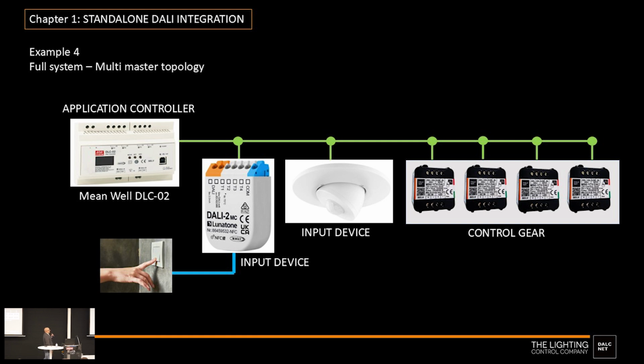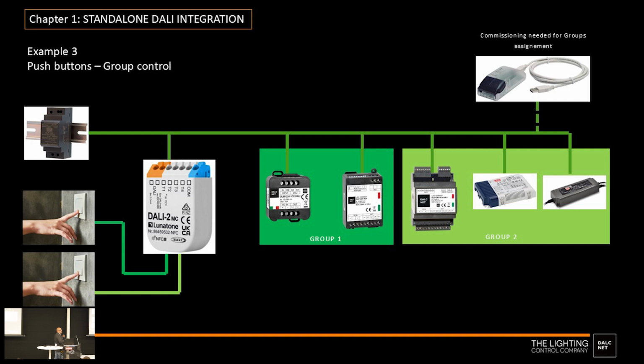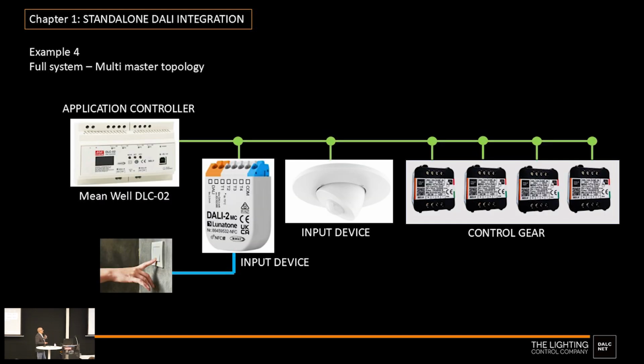Then we move to probably the most recent evolution of a DALI standalone system. With the DALI 2 introduction, DALI has created the multi-master topology configuration. In the previous example, the system was a single master application, meaning only one device controls the luminaires or control gears. In the multi-master topology, the configuration is layered on different levels.